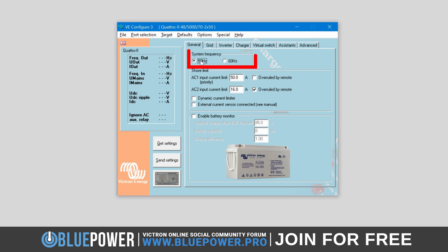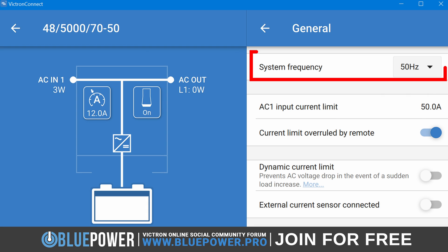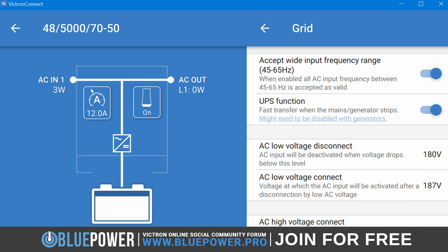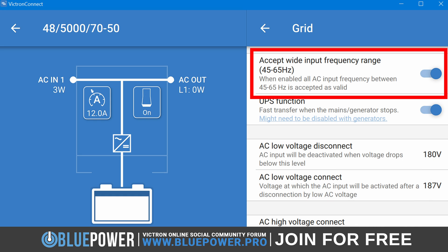With a Victron inverter, you can select the system frequency in the VE Config software or within the Victron Connect app. Note that this setting also determines the acceptable frequency range of the transfer switch if the Accept Wide Input Frequency Range setting is disabled in the Grid Settings tab.